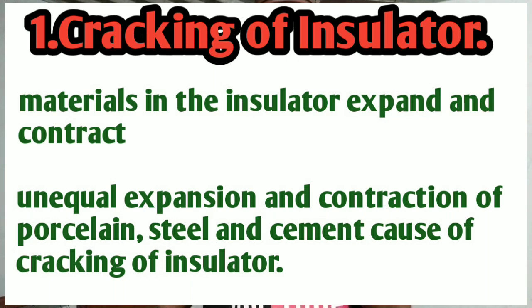Three or four, or five years later, the insulator will show leakage because the compression between the materials is going to fail over time.